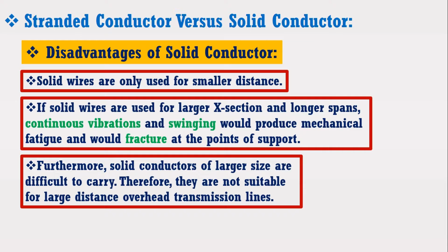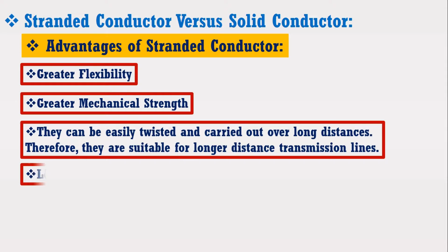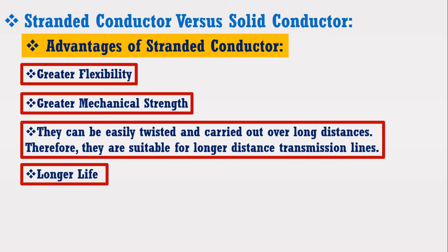In comparison to this, stranded conductors have the following advantages. Due to stranding, they have greater flexibility and greater mechanical strength. They can be easily twisted and carried over long distance. Therefore, they are suitable for longer distance transmission lines. Due to flexibility, they have longer life compared to solid conductor. As the overhead transmission line is always subjected to wind speeds and storms, if solid conductors are used, they will break due to continuous vibration. Therefore, in overhead transmission line, stranded conductors are used.